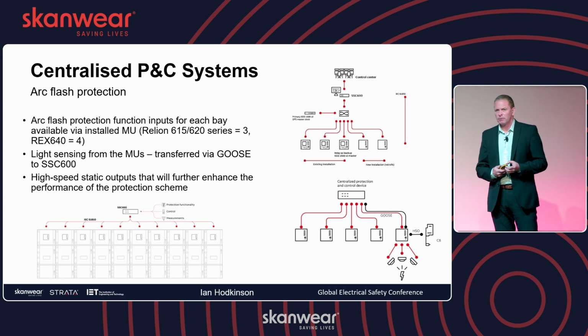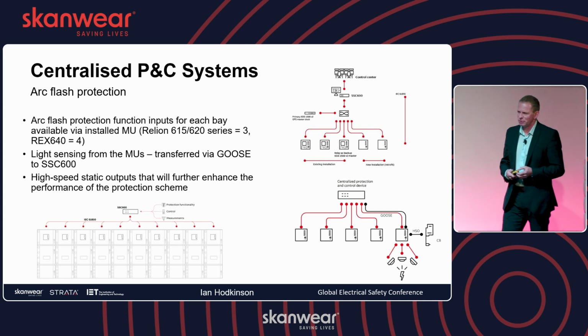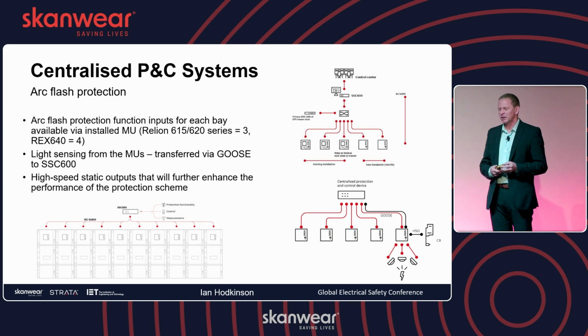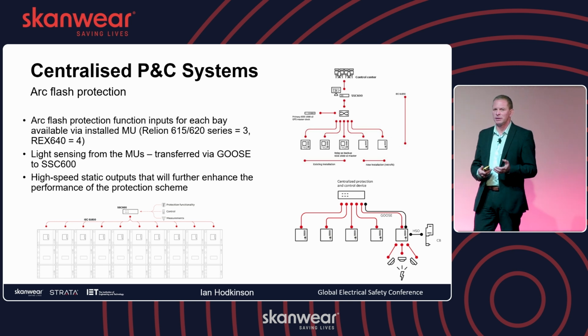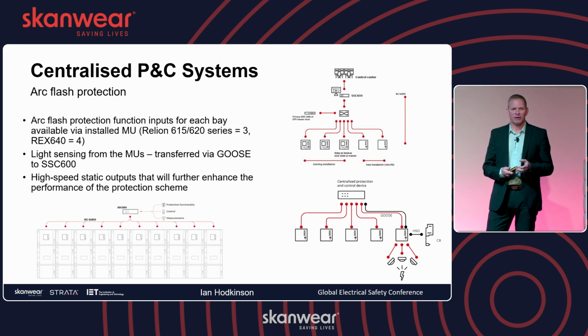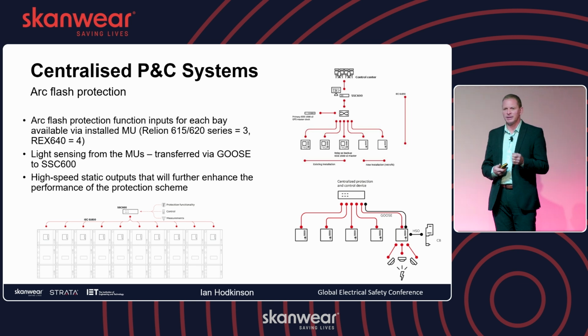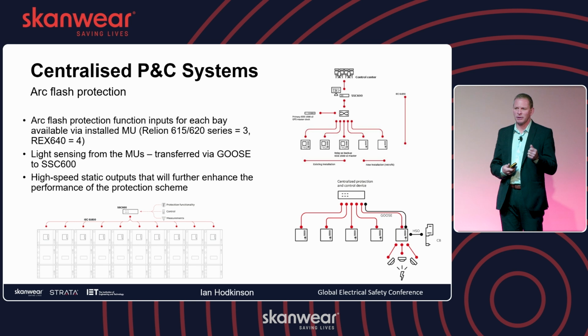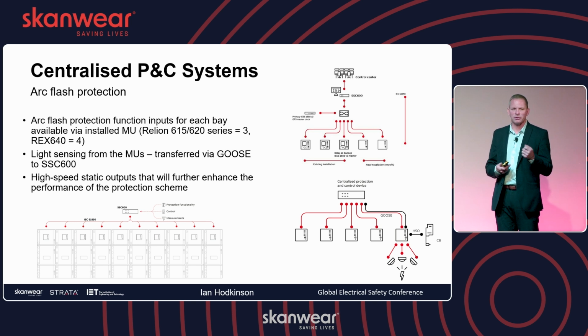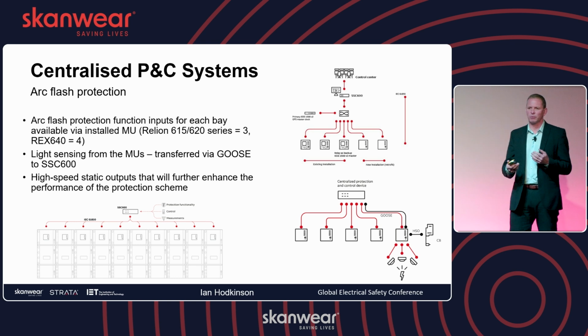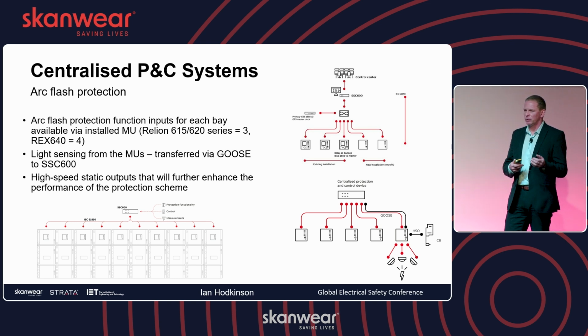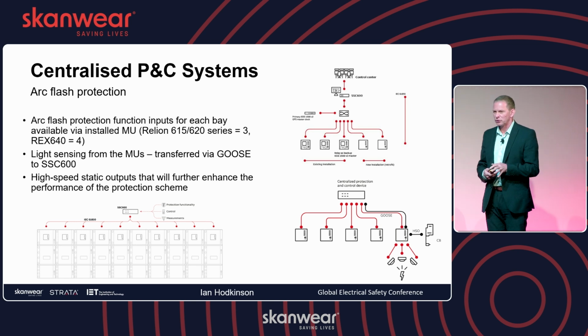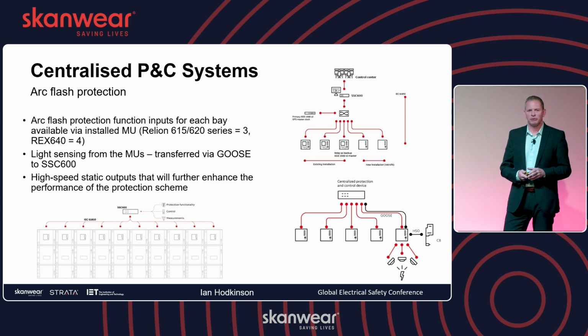We also have now what we call a centralized protection and control system. This is not specifically to arc protection, it's just a nice new way of doing this. So we have merging units instead of protection relays in each individual panel, and we have one protection device or one server with all the protection functions housed within, but the merging units do the detection of the arc and send the signal over GOOSE to the centralized protection. The protection, if it picks up the current, decides in your logic which feeders you want to open, close, whatever, and how you operate your switchgear, then that message is sent back very quickly over GOOSE to the merging unit to do the tripping command. So I just thought I'd make you aware of that, and again, there's a lot of detail to cover in just a single slide in a few seconds, but if you're interested, please come and talk to us about that.